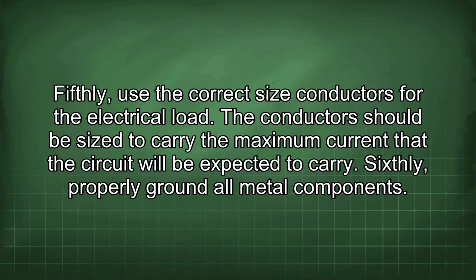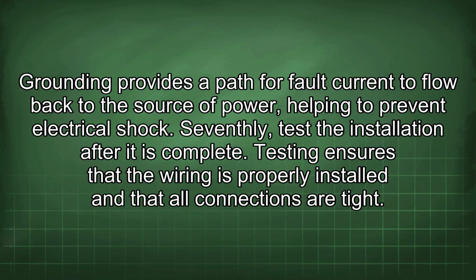Fifthly, use the correct size conductors for the electrical load. The conductor should be sized to carry the maximum current that the circuit will be expected to carry. Sixthly, properly ground all metal components. Grounding provides a path for fault current to flow back to the source of power, helping to prevent electrical shock. Seventhly, test the installation after it is complete. Testing ensures that the wiring is properly installed and that all connections are tight.